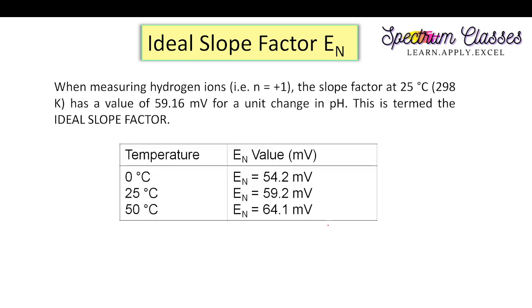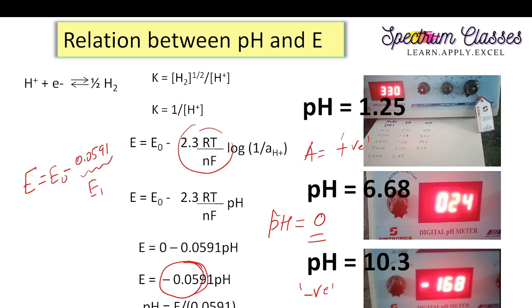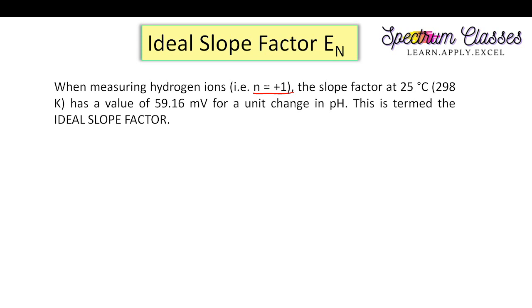Now, what is called the ideal slope factor? This value — the coefficient of pH in the equation E = E⁰ − (2.303RT/nF)·pH — is known as the slope factor. At temperature 25°C (298 K), with n = +1 for hydrogen ion measurement, the slope factor has the value 59.16 millivolts per unit change in pH. This is termed the ideal slope factor.